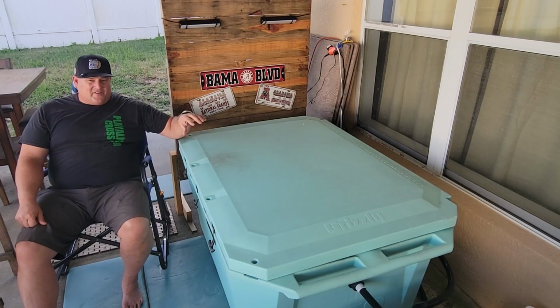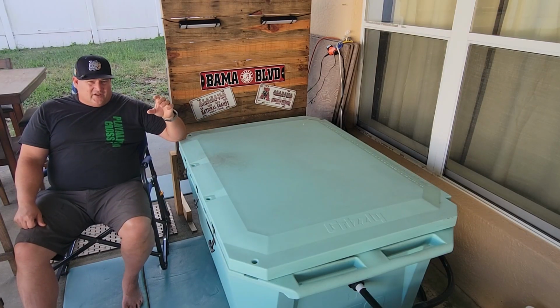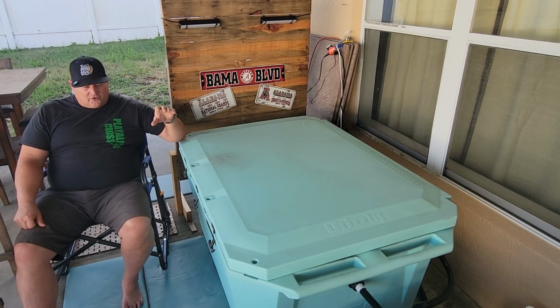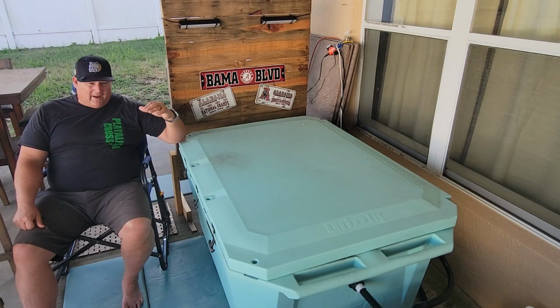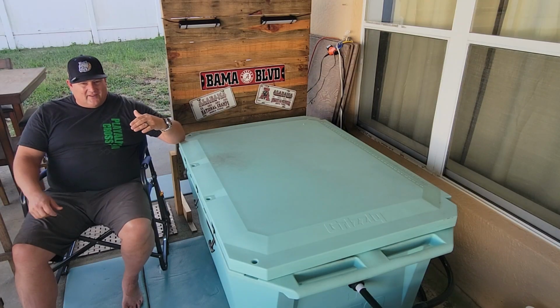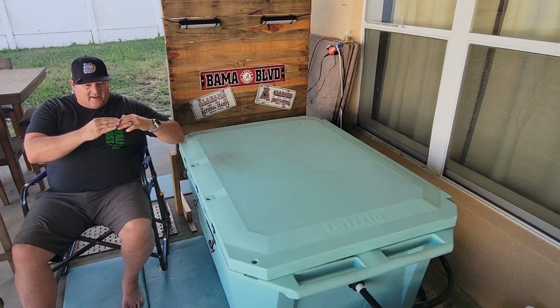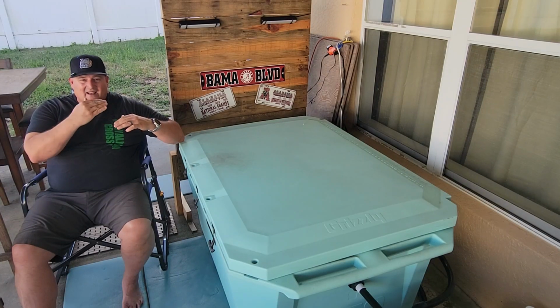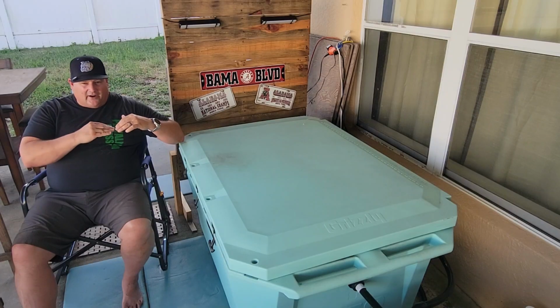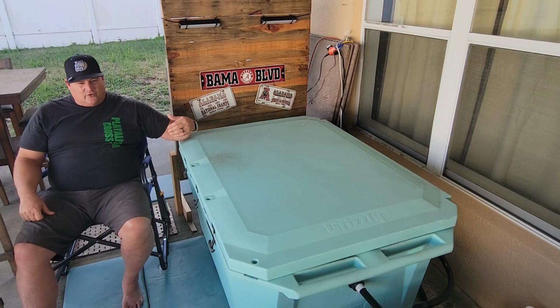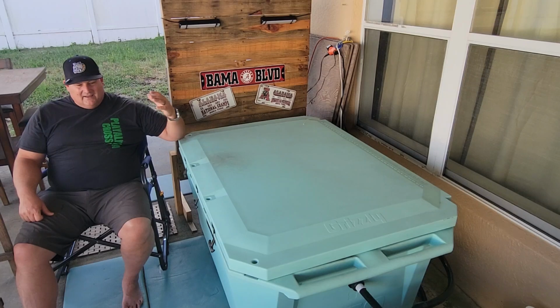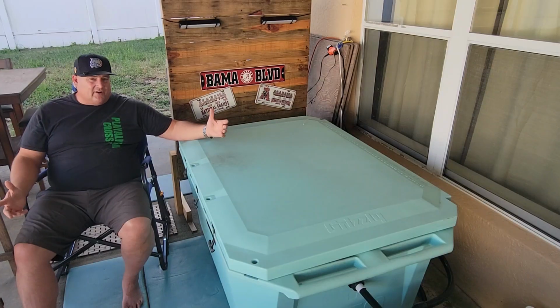With this Active Aqua chiller, you're going to see a variation in temperatures. Don't think your chiller's messing up, it's not, it's doing that by design. I have mine set on 45 degrees, and it will bounce up to 47 and back down to 45. That's by design to save your compressor. If it cut on and off hard every time it hit the exact set temperature, that would damage the compressor. So they set it with a 2 degree buffer, giving it time to equalize between cycles.